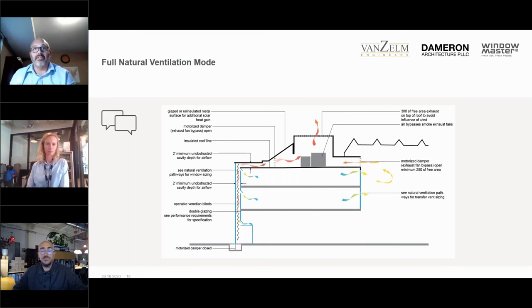When conditions are right, all windows open. Once temperature, humidity, and dew point in the spaces start to get elevated, we transition to mixed mode ventilation. Because this building had an atrium, we were required to have atrium smoke exhaust fans, so all the air in the building had to get exhausted out through the same penthouse level in an atrium smoke event. Since that equipment was there for smoke control, we utilized the same equipment and fans for mixed mode ventilation.